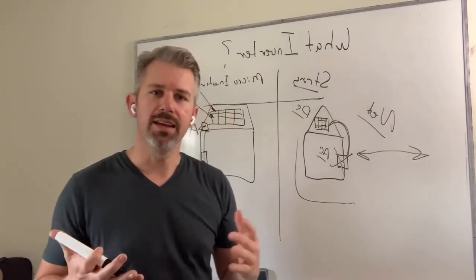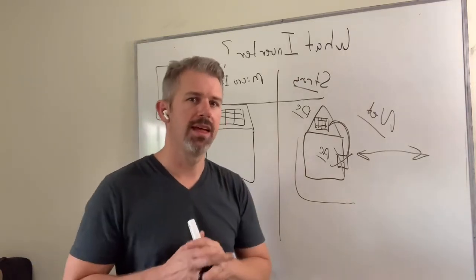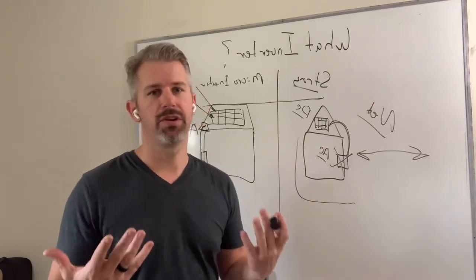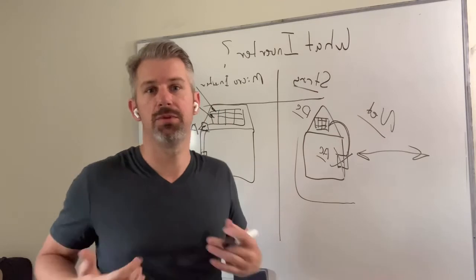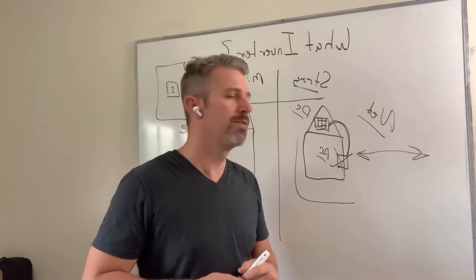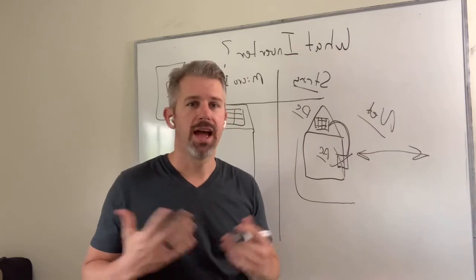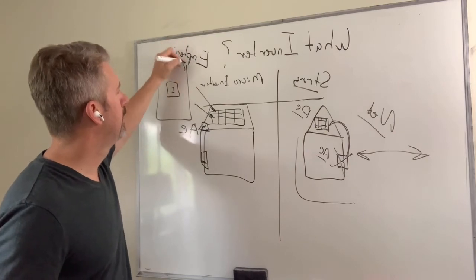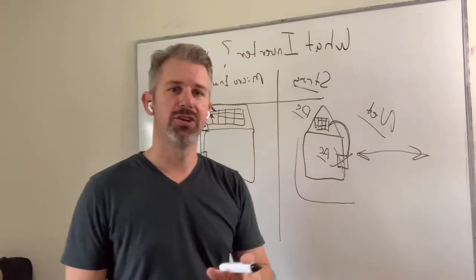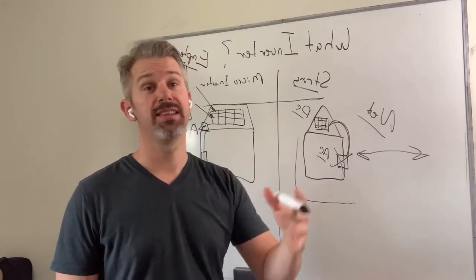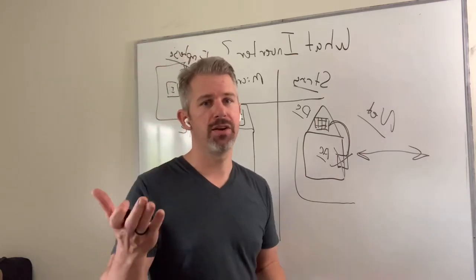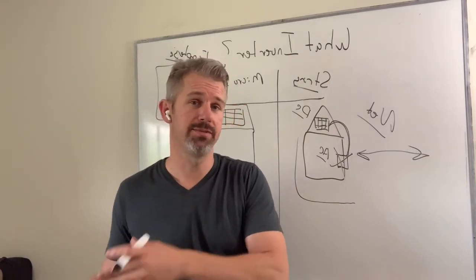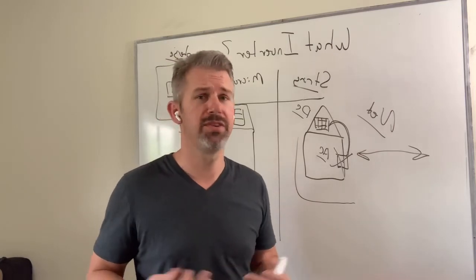Microinverters in the early days had a much higher fail rate than they do today, compared to string inverters. So we were very loath to use them for a while just because we were super concerned about that. Over the years, they've gotten much, much better. And the clear leader in this space is Enphase Energy. What they offer is a 25-year warranty on their equipment, parts and labor, which is pretty compelling. Because your panels generally have physical warranties of 10, 12, expandable to 20, but production warranties of 25 to 30, the operating life of a solar system is very long.